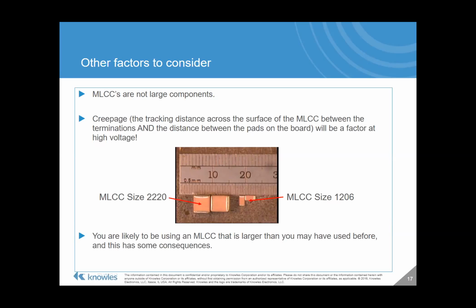Just this week, we've had discussions with a customer who was trying to use a component 5 millimeters long. Looks like it does everything he wants. He needs a minimum creepage of 18 millimeters to meet his standards. That's going to have an effect on component selection. It's going to have an effect on board design. And ultimately, it looks like he's probably going to have to just redesign his board to make sure the tracks, when they come out of a coated area, are at least 18 millimeters apart. So you're likely to be using a multi-layer that is larger than you've used before.